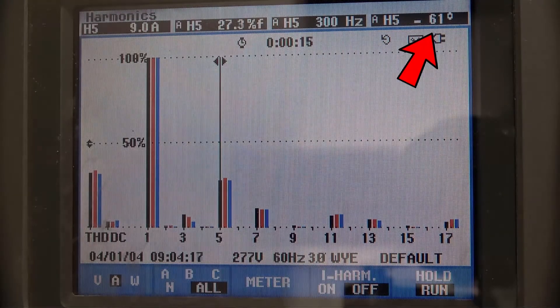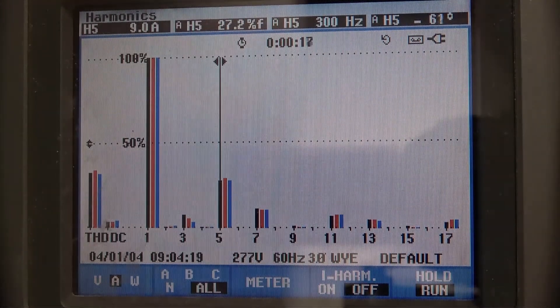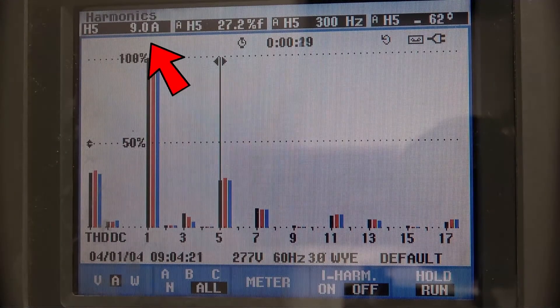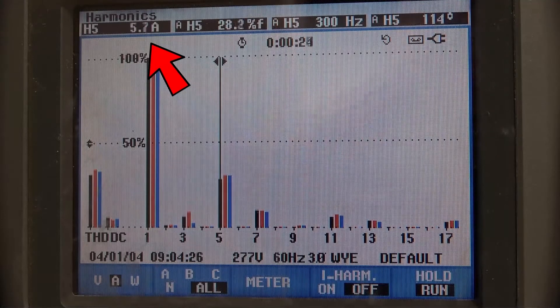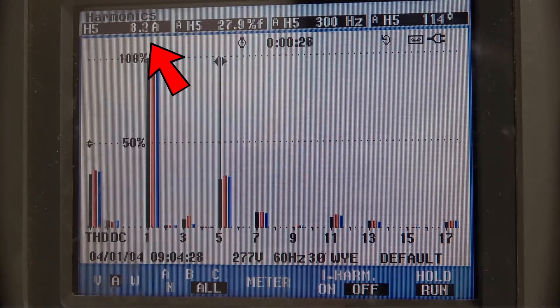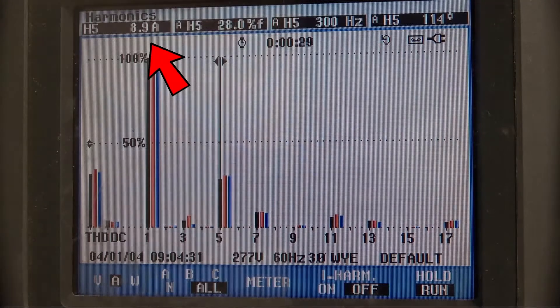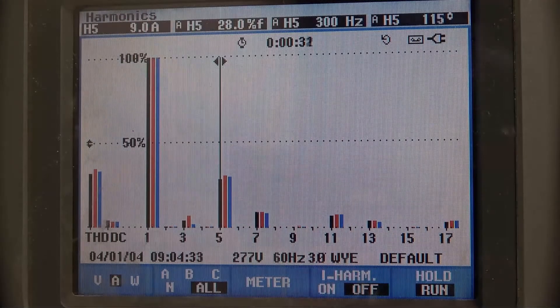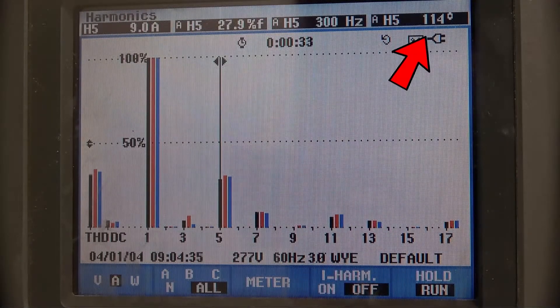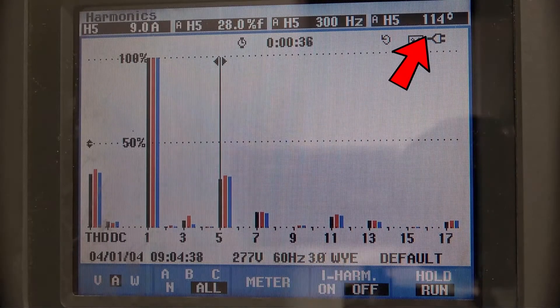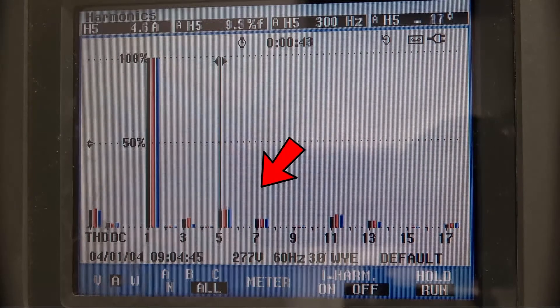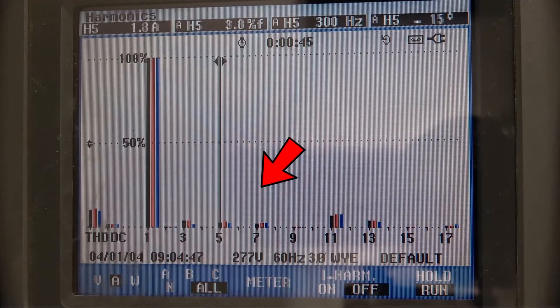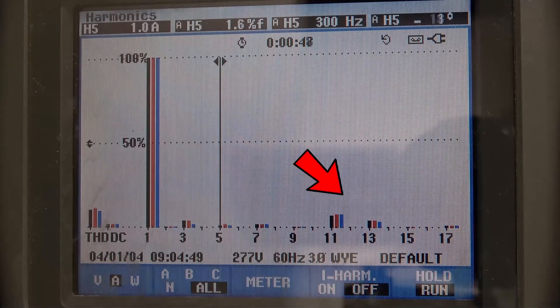Now if we turn that drive off and turn drive number one back on, we see the harmonic currents from that drive come in at about the same magnitude — almost 9 amps again — but the phase angle is about 114 degrees. So when we put both drives on together, the fifth and seventh cancel out, but the eleventh and thirteenth basically add up together.